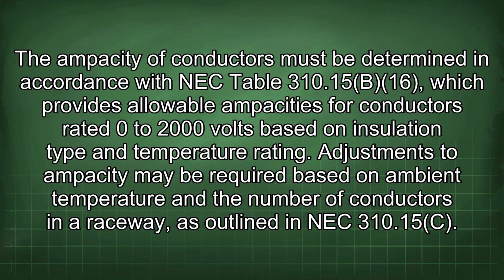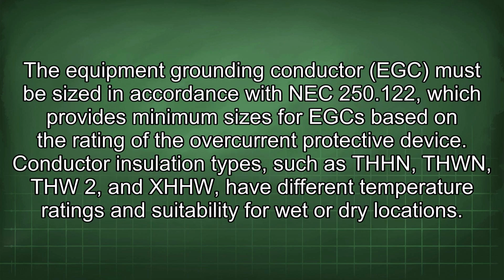The ampacity of conductors must be determined in accordance with NEC Table 310.15(B)(16), which provides allowable ampacities for conductors rated 0 to 2000 volts based on insulation type and temperature rating. Adjustments to ampacity may be required based on ambient temperature and the number of conductors in a raceway, as outlined in NEC 310.15(C). The equipment grounding conductor (EGC) must be sized in accordance with NEC 250.122, which provides minimum sizes for EGC based on the rating of the overcurrent protective device.